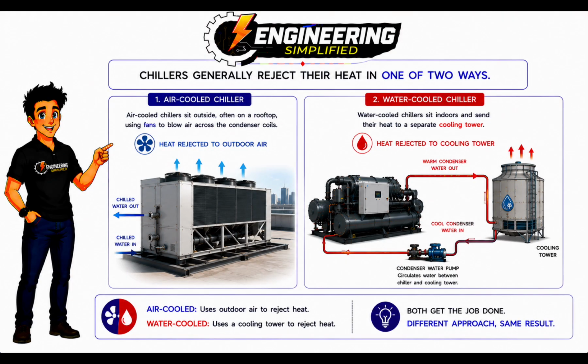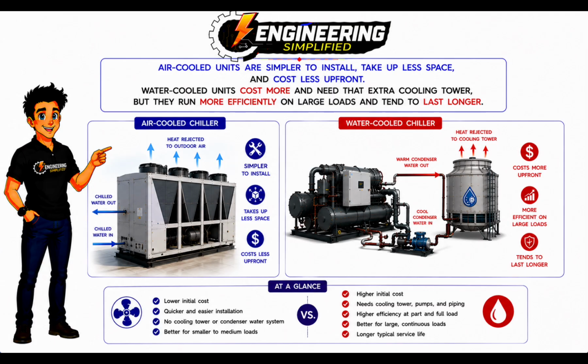Chillers generally reject their heat in one of 2 ways. Air-cooled chillers sit outside, often on a rooftop, using fans to blow air across the condenser coils. Water-cooled chillers sit indoors and send their heat to a separate cooling tower. Air-cooled units are simpler to install, take up less space, and cost less up front. Water-cooled units cost more and need that extra cooling tower, but they run more efficiently on large loads and tend to last longer.